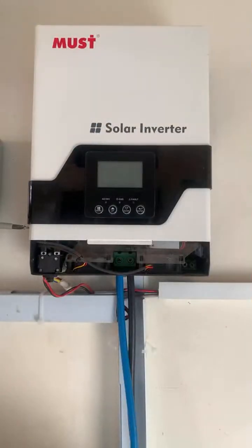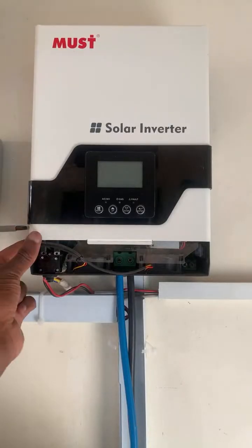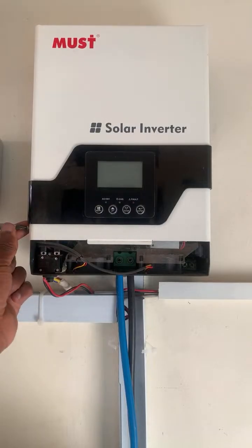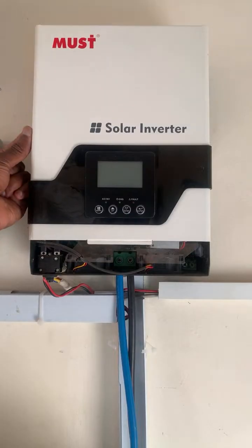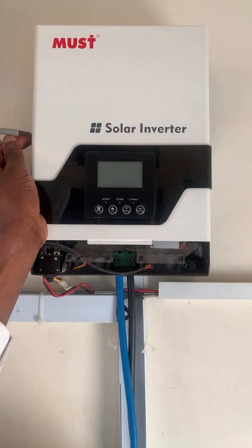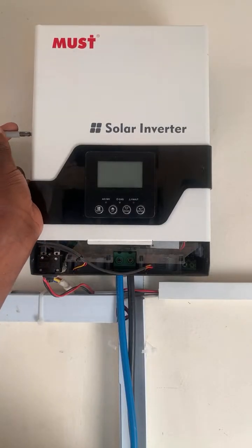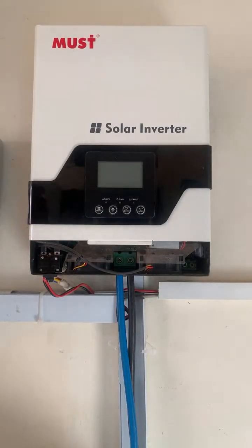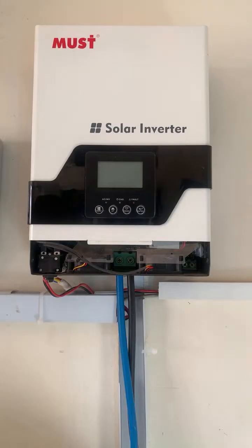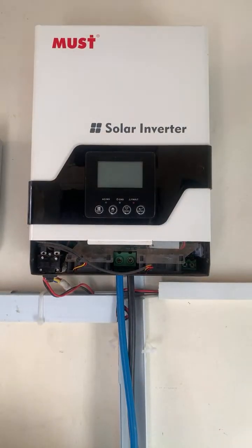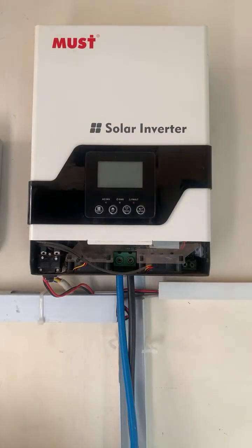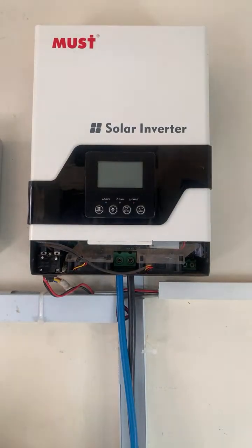You'll notice that from the inverter all the way to the battery, including that connection at the inverter, there's a very huge allowance for you to connect huge cables. That is done intentionally, my top boss, very intentionally, so that you can curb any chances of overheating. Why will those cables overheat? Simply because DC current, direct current, requires huge sized cables because of losses, and especially if you're compensating for distance, you must ensure that you compensate for that.